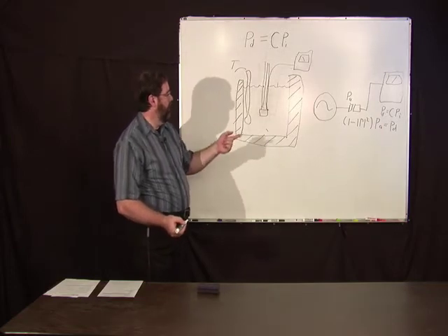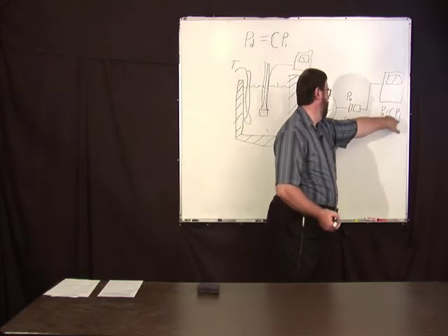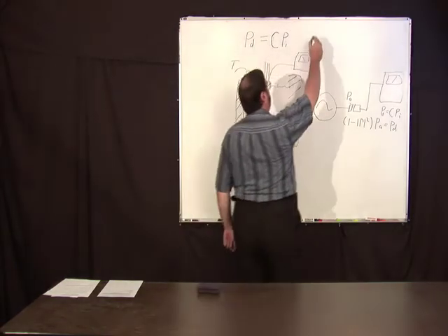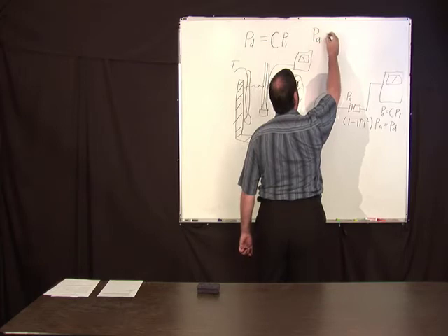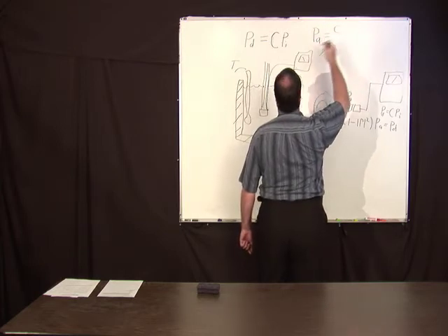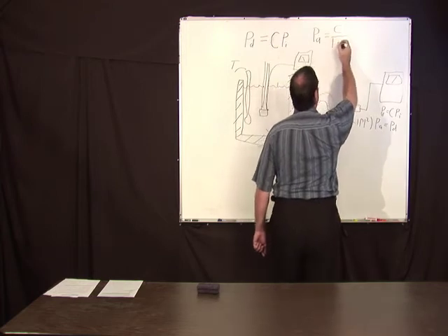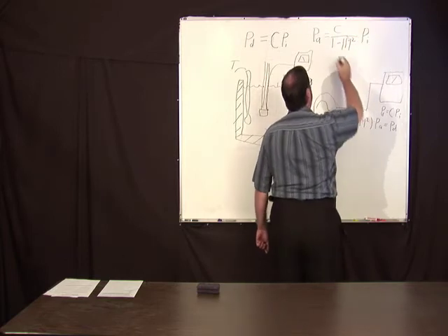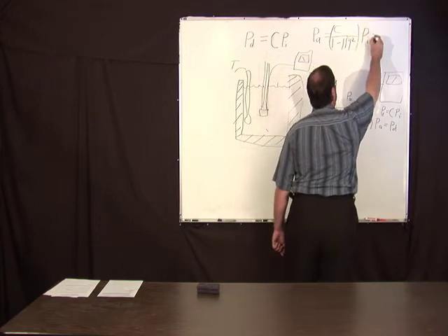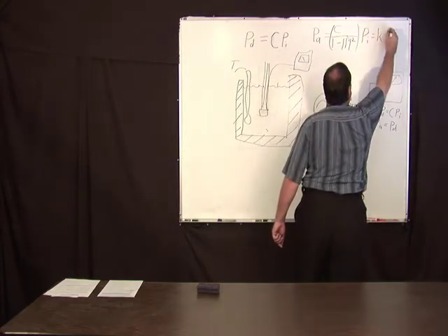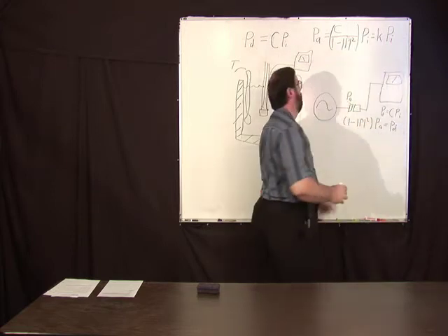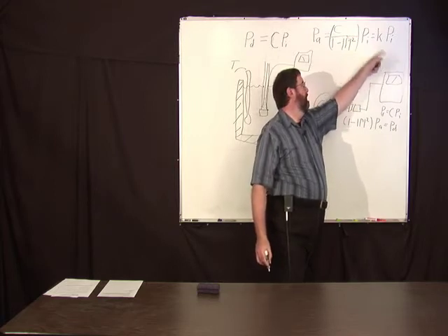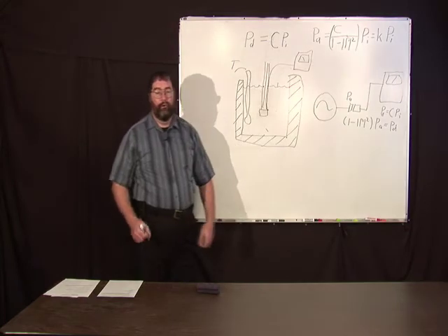The power actually delivered to the power sensor is going to be 1 minus gamma reflection coefficient squared times the available power. That's equal to the power delivered. So the available power equals this constant we got from calorimetry divided by 1 minus the reflection coefficient squared times the indicated power. This thing here, we'll just call that K.